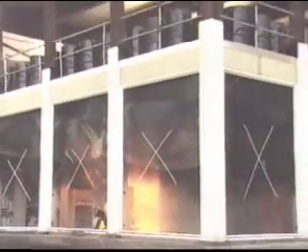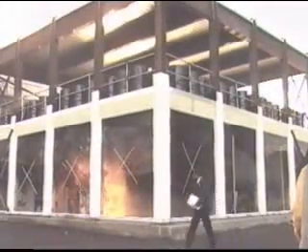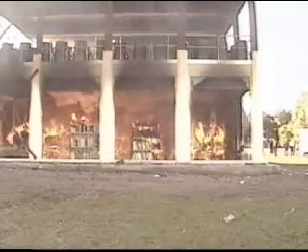At approximately 7.5 minutes, the glass cracked in the window, and shortly after it fell out. From this point until about 18 minutes after ignition, windows continued to crack and fall out. Finally, the sprinklers were turned on and the fire extinguished. For this test, the steel beams were partially protected with fire protection material, but the composite floor slabs were unprotected. Inspection of the building following the test revealed no damage to the beams or the floor slabs.